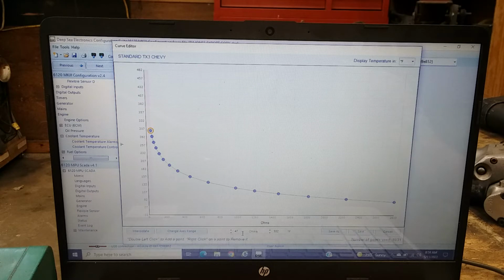And you'll notice this one actually reads in degrees Fahrenheit. So we go from 307 degrees down to about 60, maybe 78, 80 degrees. You can just click that and find out - 77 degrees. So you've got a much wider range. The other one only went to like 400 or maybe 450 ohms. This one goes out to 2,800 ohms.